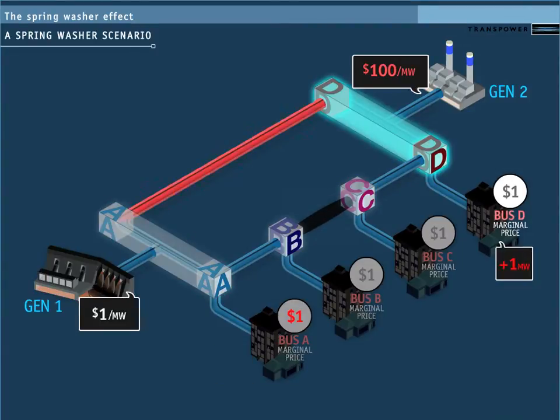For bus D, because AD is limited, the next megawatt of load cannot come from generator 1, so it would have to be supplied by generator 2 for $100. So the marginal price at bus D increases to $100.